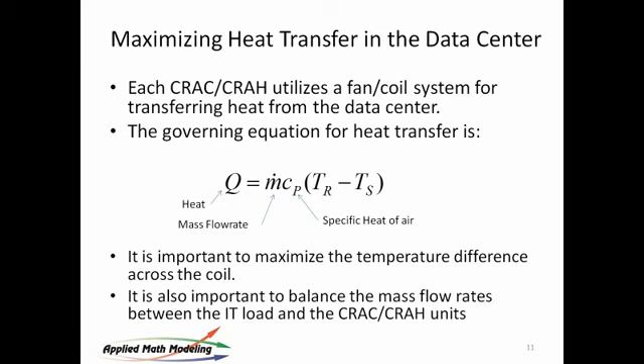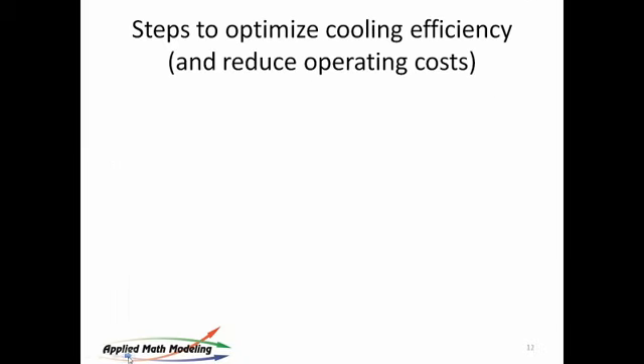So it's important to maximize the difference between the coils, between the temperature across the coils, to get good heat transfer. It's also important to keep an eye on that mass flow rate, particularly in the case of the cooling systems, because if the mass flow rate gets too high, the delta T by definition will drop. So it's important to understand that relationship and how it works.